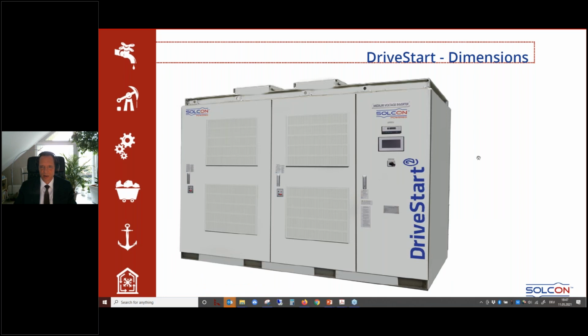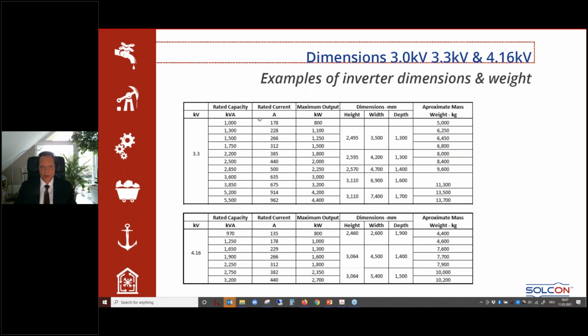Okay, DriveStart, some words about the dimensions. Okay, 3.3 kV for the inverter dimensions. The biggest one, 5.5 MVA, 962 amps, which is unusual at this kind of voltage, but the height would be 3 meter, width 7.4 meter, and depth 1.7 meter. But let's say if we're talking about the smaller, where you see more, the 3.3 is height 2.5 meter, 3.5 meters width, depth 1.3 meter. 4.16 kV, which is interesting for the United States. In the smaller ratings, 2.5 meter height, width 2.6 meters and 1.9 meters depth. Please forgive me, I have not transferred this into imperial dimensions, inches and feet. But you can do the math on your own.